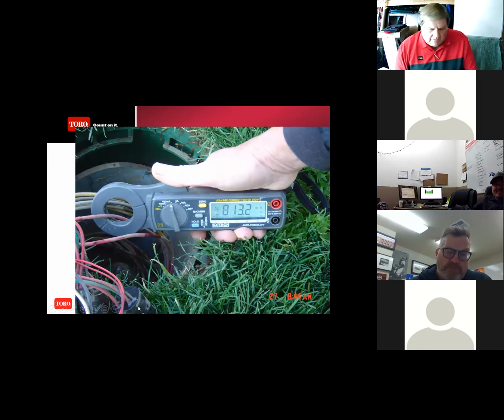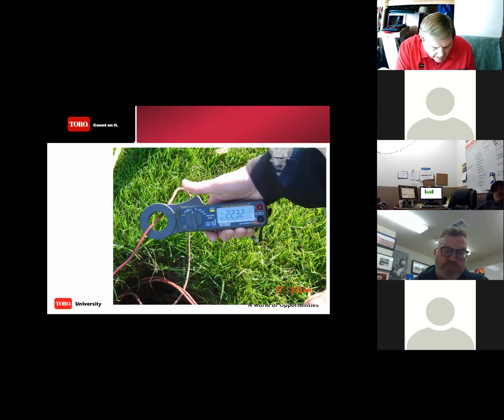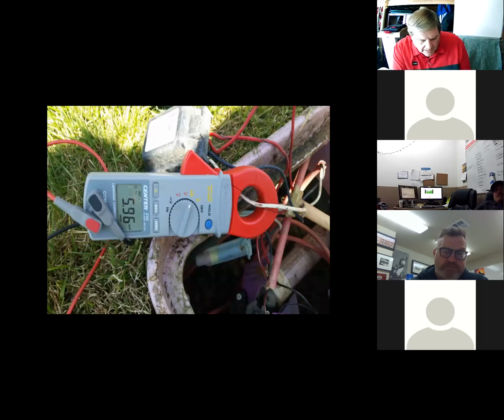And if that thing got hit with lightning or got hit with a surge, it will short to earth ground, and that's causing that high current draw. But it's a matter of just bending over into the valve box, grabbing the wire path, and separating each path so you can clamp around, as you see in the photograph, one wire at a time. And you're just going to go through that 2-wire path from valve box to valve box to valve box, and just keep reading. I'm back to 223 again.